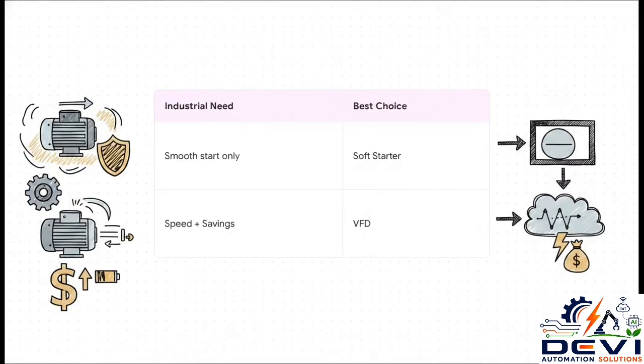So, boiling this entire selection guide down, it really just comes to one straightforward question. Do you simply need a smooth start to protect your mechanical parts and then it's just going to run at full speed? If yes, the research says choose a soft starter. But if you need to control the speed of the process throughout the day and want to capture energy savings by slowing that motor down, a VFD is 100% the way to go. It really is that simple.